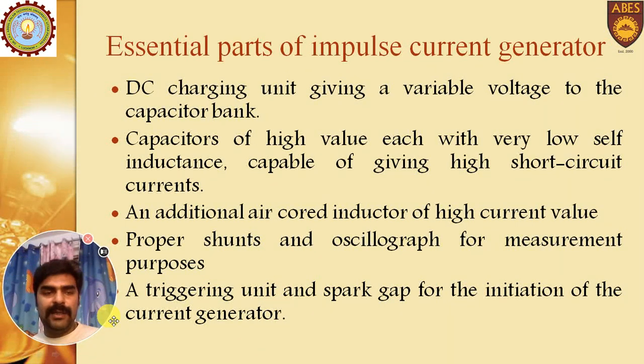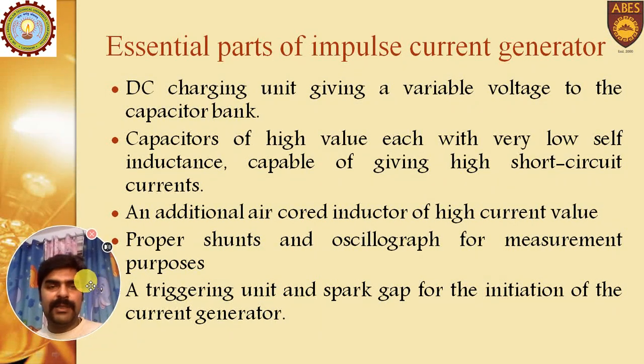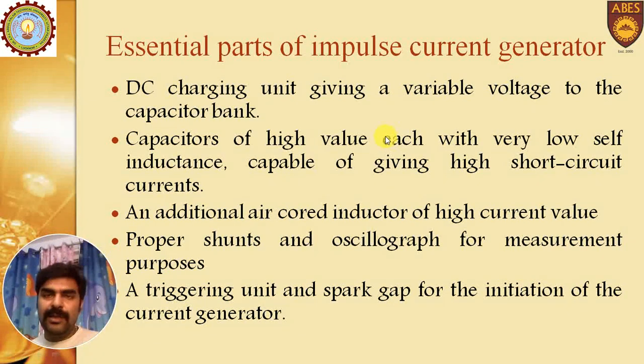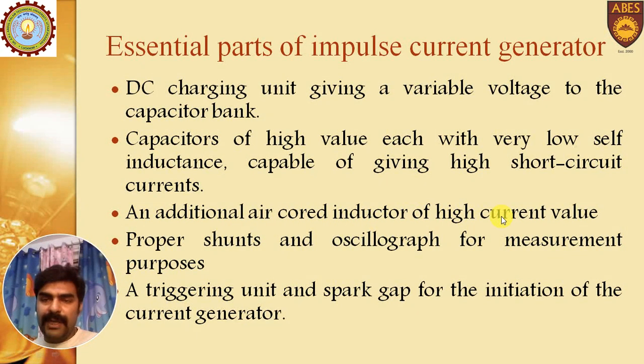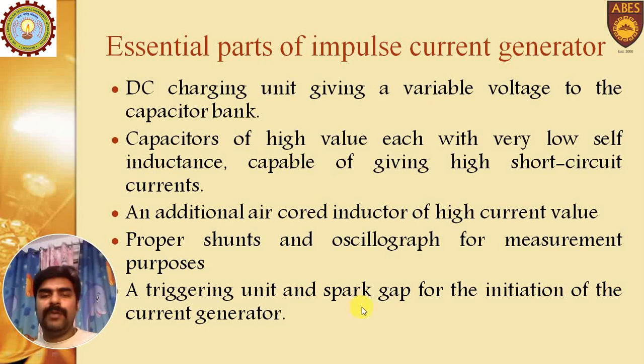The next question covers the essential parts of an impulse current generator. The main components are: a DC charging unit that provides variable voltage to the capacitor, a high-value capacitor, a low-inductance air-core inductor of high current value, a proper shunt and oscillograph for measurement, and a triggering unit with spark gap for initiation of the current generator.